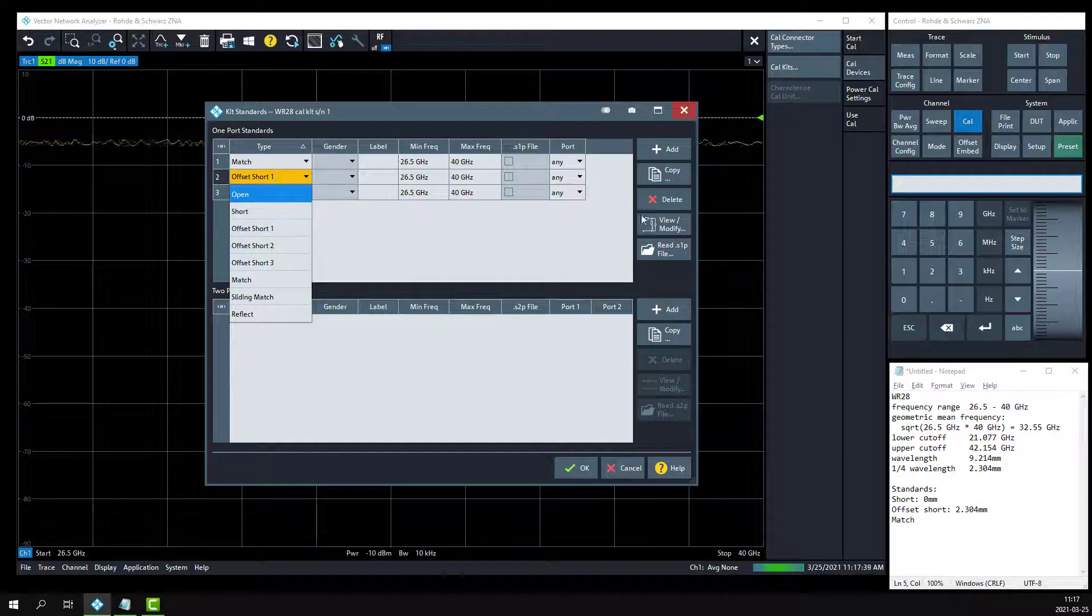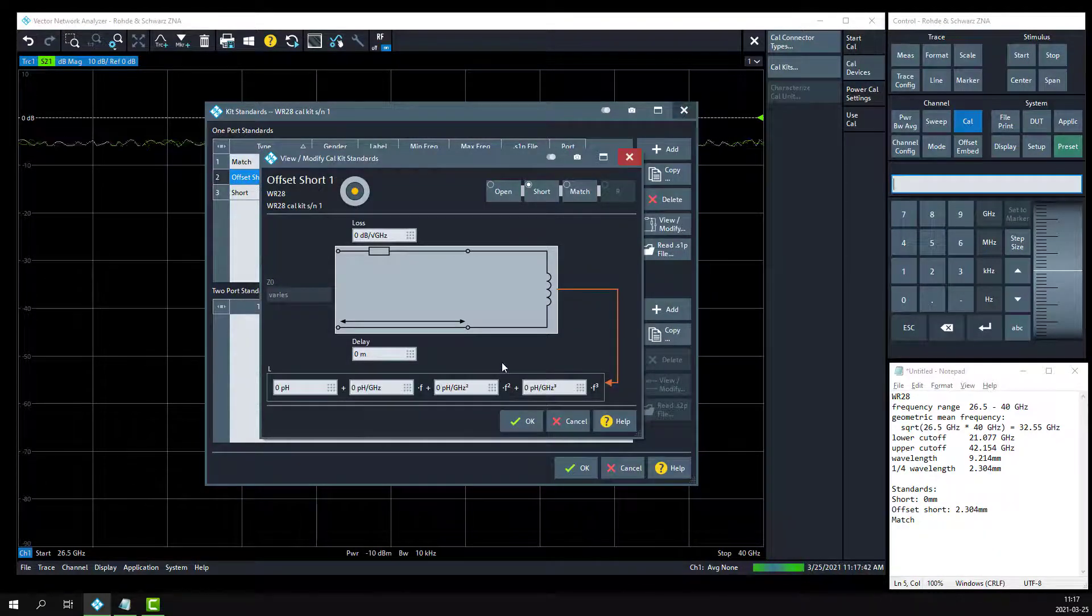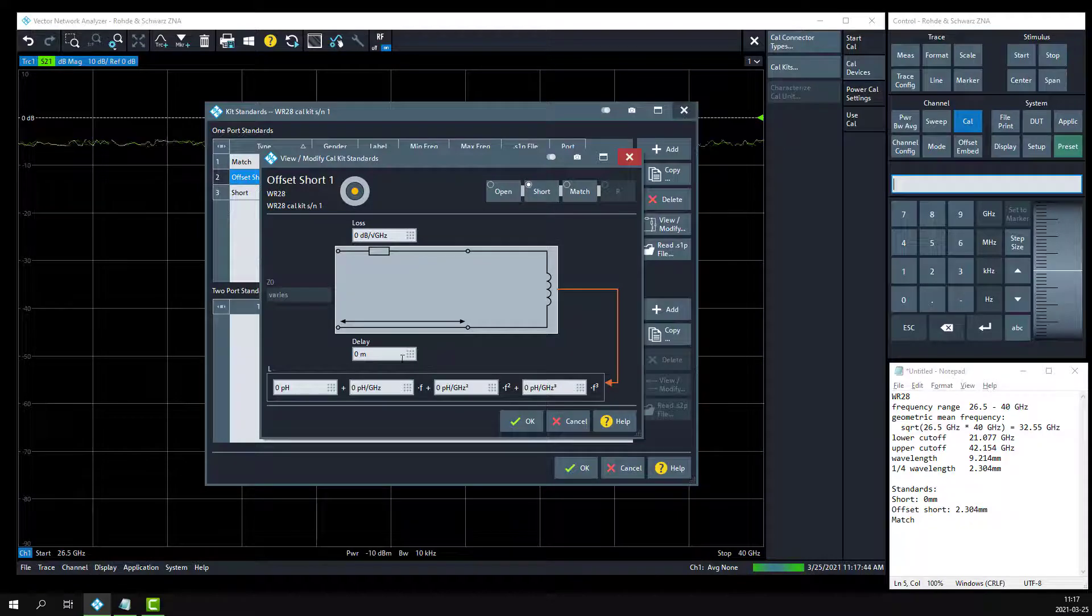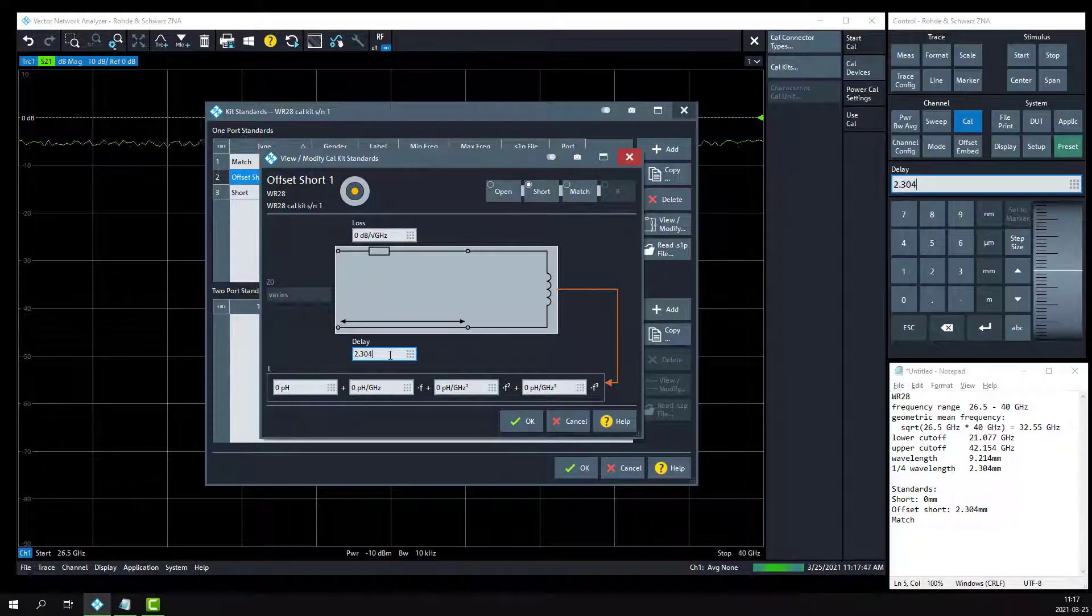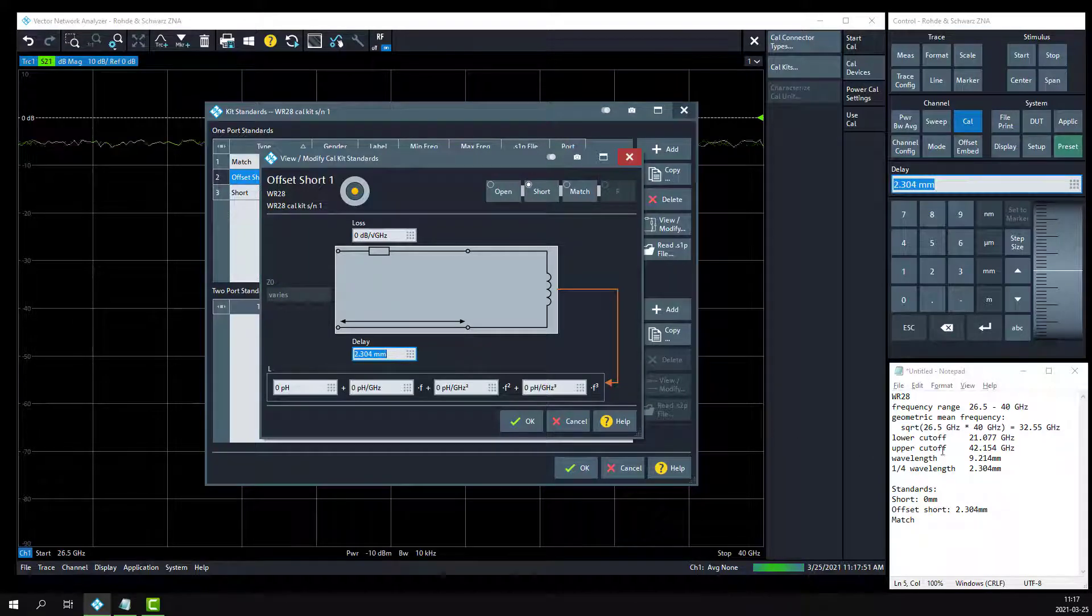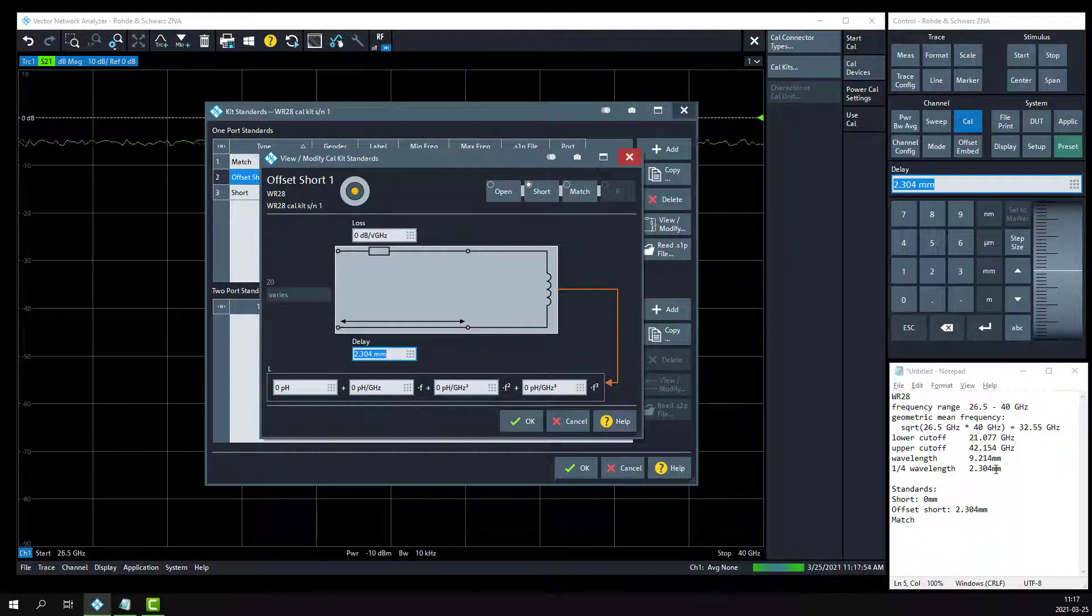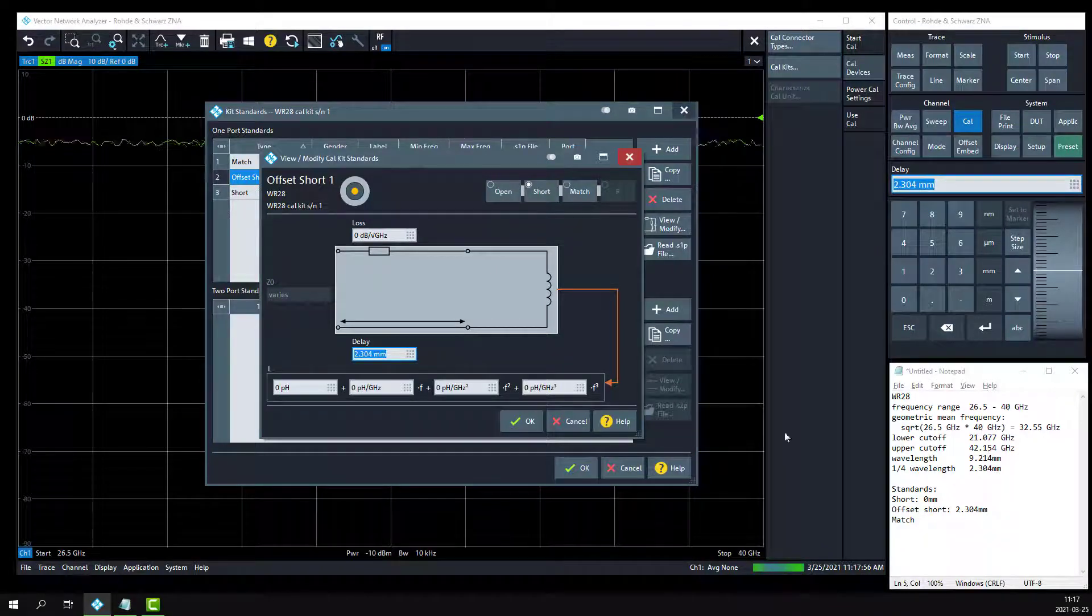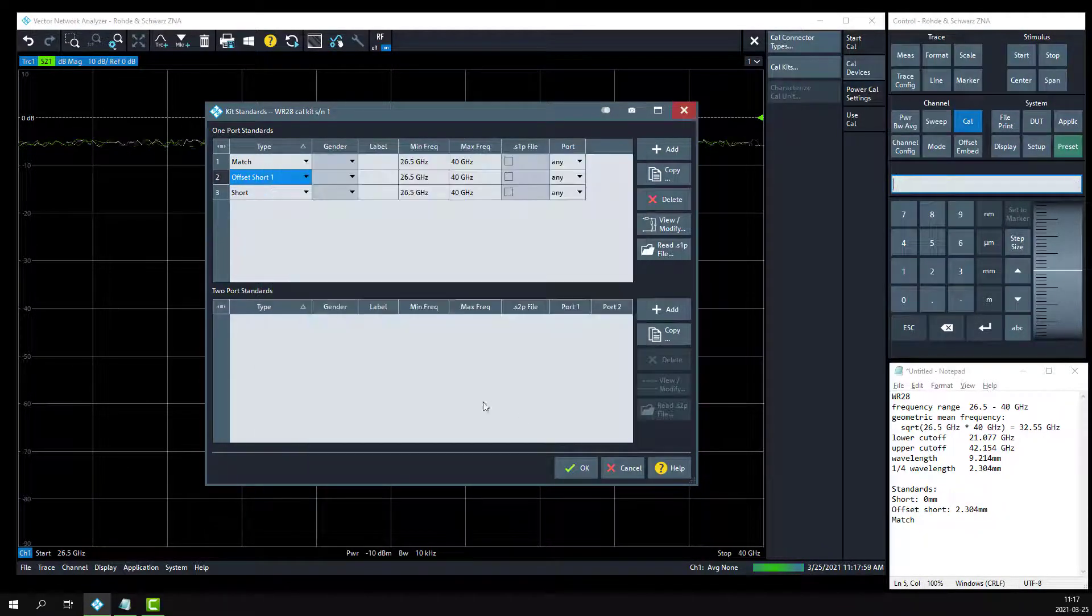For offset short, we are using a quarter wavelength at the geometric mean frequency of 32.55 gig. That will be 2.304 millimeters, if we do the math correctly. We probably actually want to measure the mechanical length of that shim using a set of calipers, rather than relying on this calculation. That will give us the most accurate measurement. Click OK.